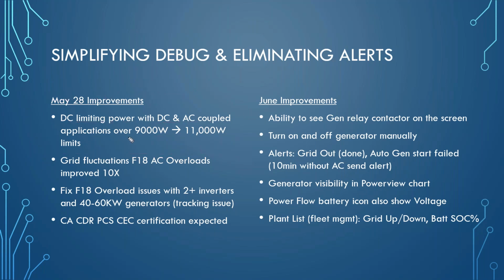Because of that, the system used to curtail your DC production to make sure the amount of power going through your grid breaker did not exceed 9,000 watts. We fixed that so you can throw all the AC coupled power out there in addition to however much power it can make on the DC side at the same time, up to 11,000 watts instead.